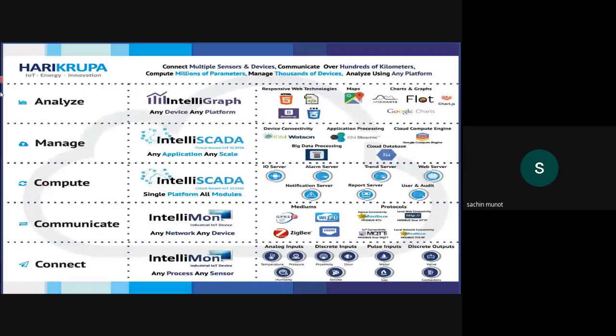So the entire architecture flows from the bottom. First it will connect to the IntelliSCADA platform. How will it connect? The IntelliMon device has provision for analog inputs, so temperature, pressure, or humidity sensors can connect to analog inputs.